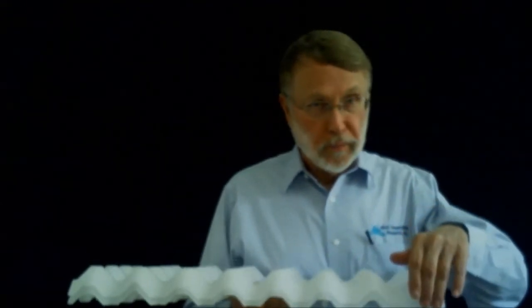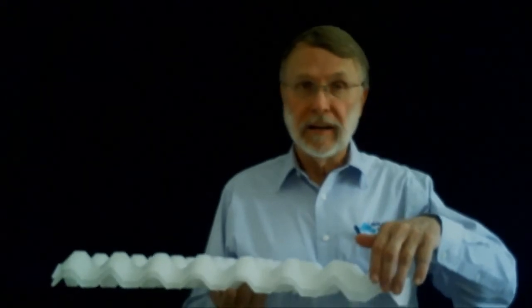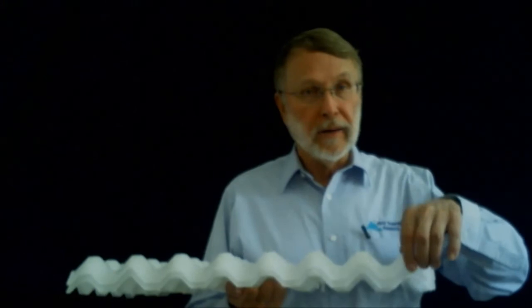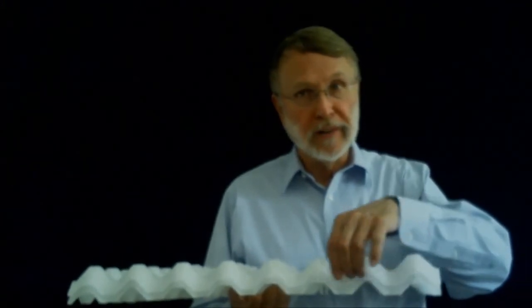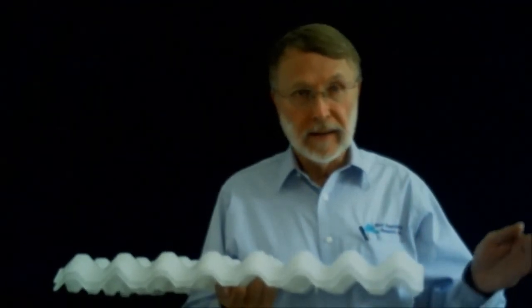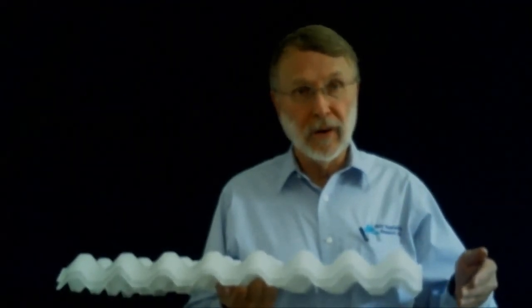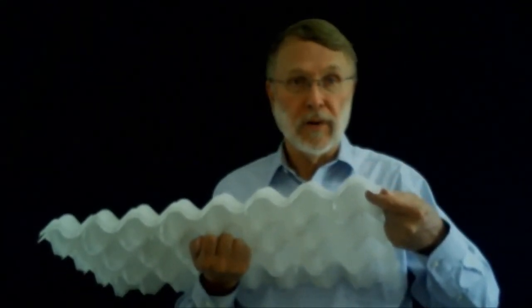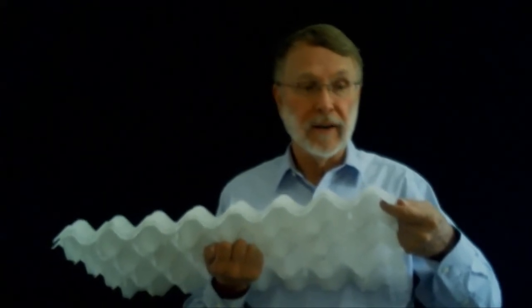The plates here are installed in the separator in this horizontal direction, and the water flows through horizontally. As it does so, any oil droplets on the inlet side of the oil-water separator rise up and meet the underside of the plates here, and they stick there by van der Waals forces, which are very weak molecular level forces.